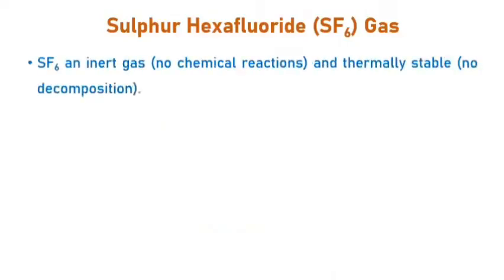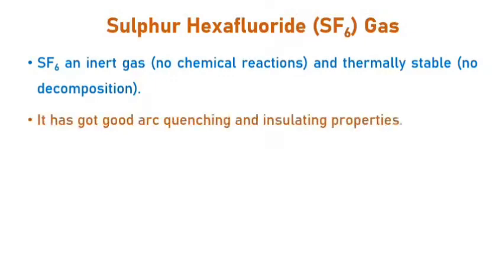SF6 is an inert gas and a thermally stable gas. When I say inert, it means there is no chemical reaction that will occur, like in mineral oil. In the previous video, we were discussing oil circuit breakers, where oil is used as an arc quenching medium. So whenever the oil quenches the arc, carbon particles will be produced. So there are some chemical reactions in mineral oil, but no such problem in SF6 gas. And thermally stable means there is no decomposition that can occur in the SF6 gas.